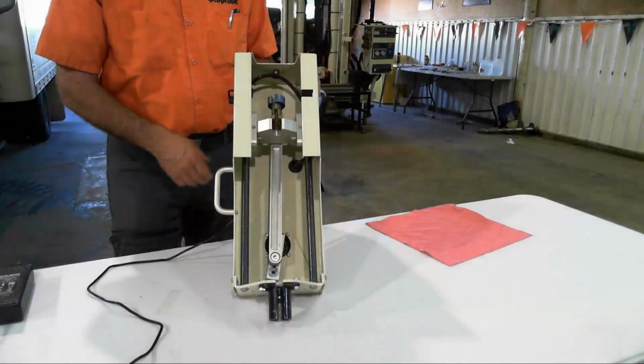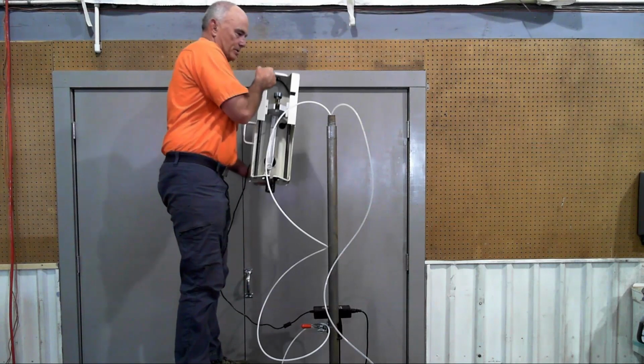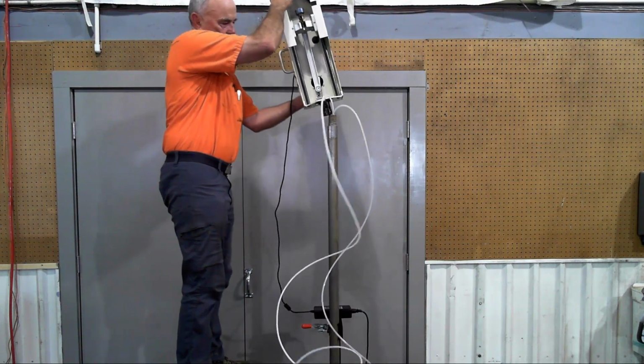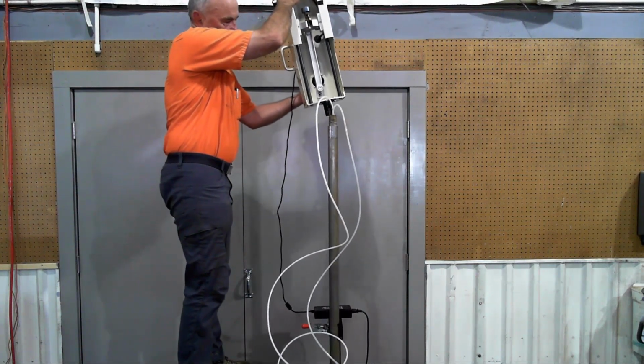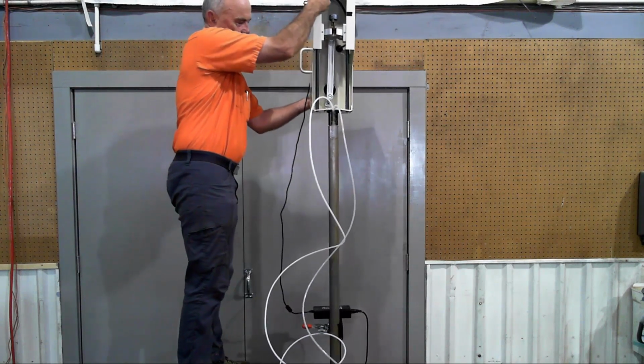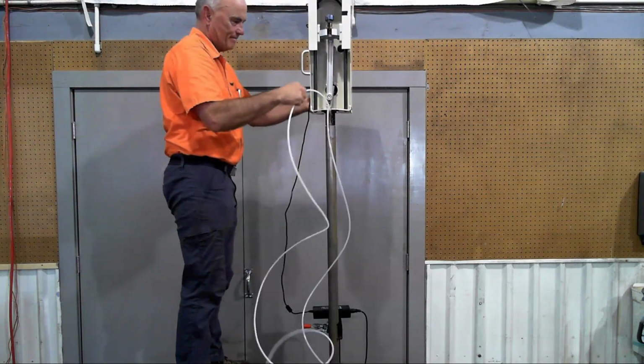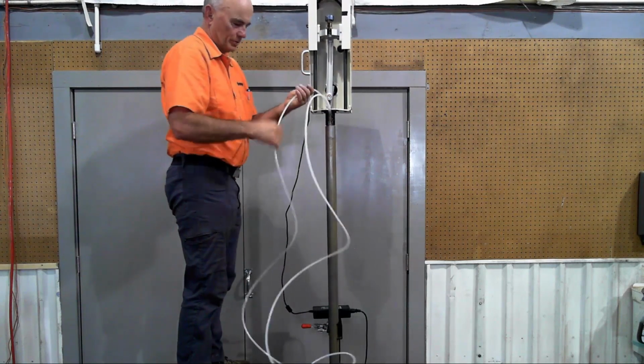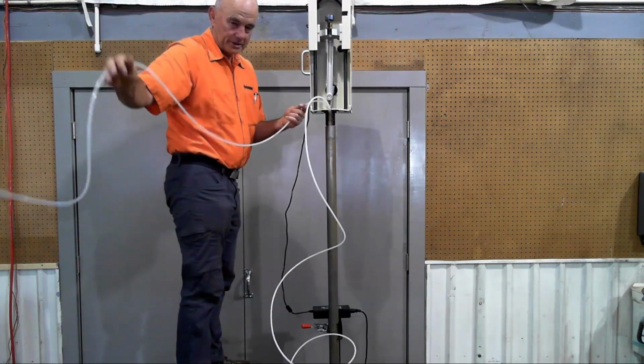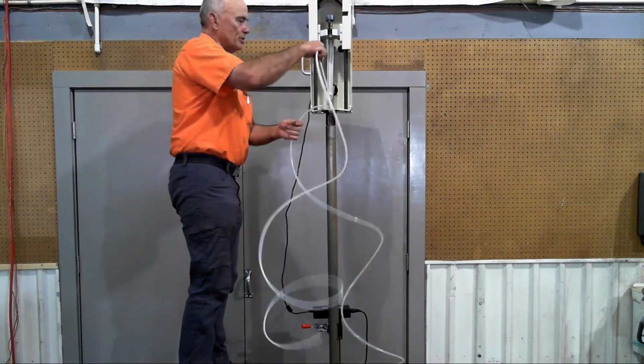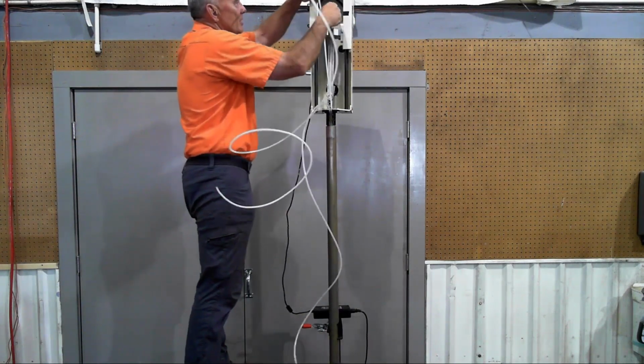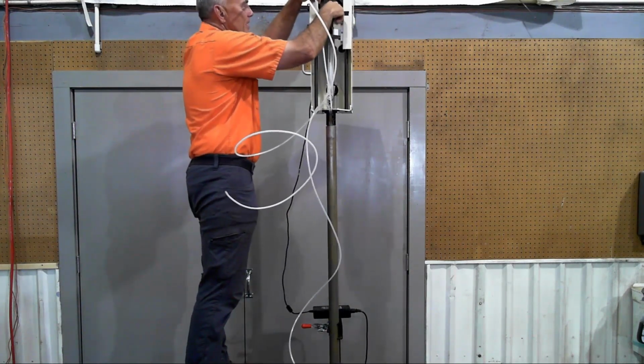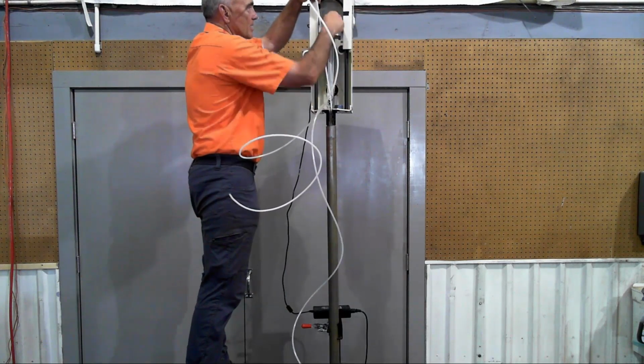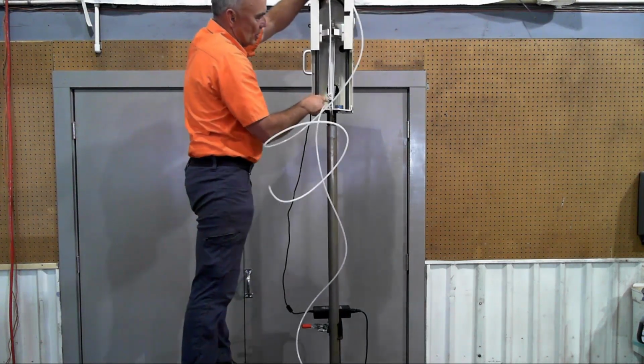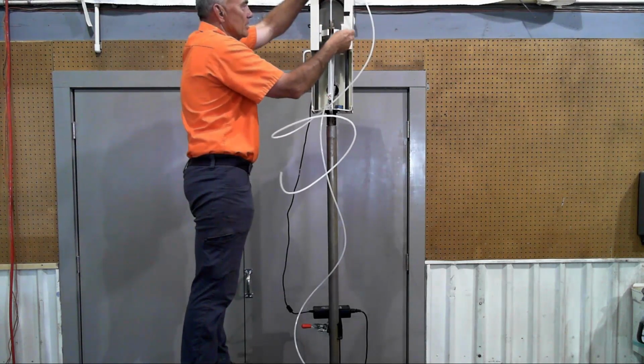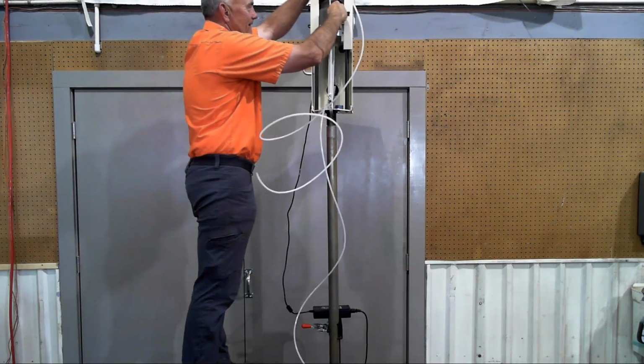We will now mount the actuator on top of the rods. With the 1.75-inch slotted base adapter, you can bring the tubing through the slot so it does not get pinched by the actuator as it is set on top of the rods. Once we have selected the stiffer sample line, we are ready to install it in the actuator, which will also be in the bottom position of the stroke. We will remove the slotted top nut and tubing wedges. We can now place the tubing through the slotted section and replace the securing wedges around the tubing and begin to reconnect the slotted nut.